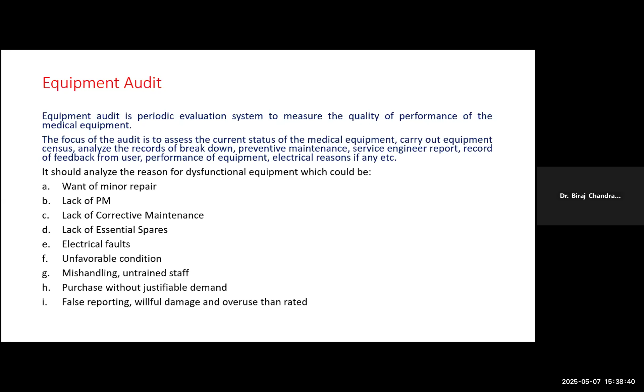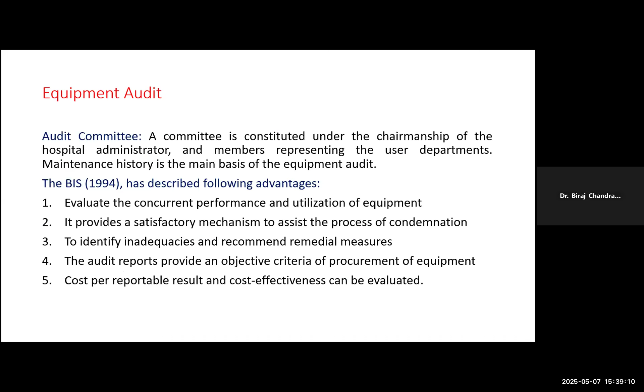The BIS has described the following advantages of the equipment audit: evaluate the concurrent performance and utilization of the equipment. It provides a satisfactory mechanism to assist the process of condemnation, to identify inadequacies and recommend remedial measures, and to audit reports. The audit reports provide objective criteria for procurement of the equipment, and cost per reportable result and cost effectiveness can be evaluated. So the equipment audit has so many advantages.